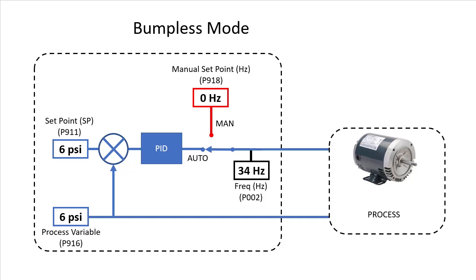That's where bumpless mode comes in. When switching from manual to automatic mode, it simply reads the current process variable and puts it in the set point.